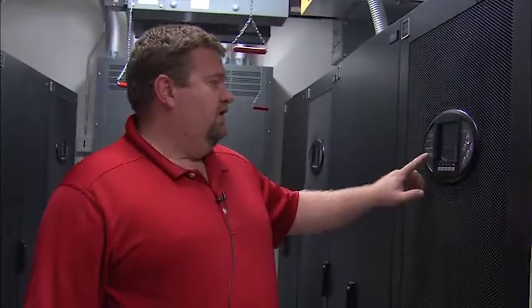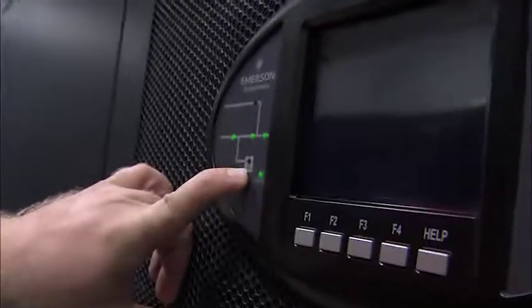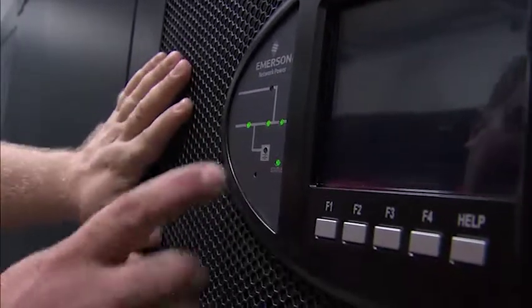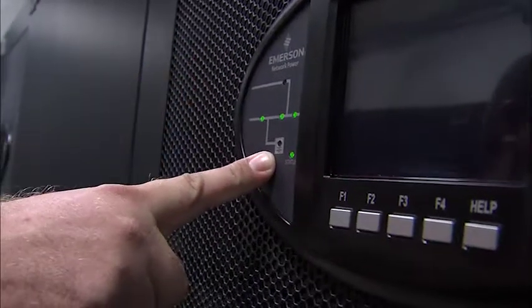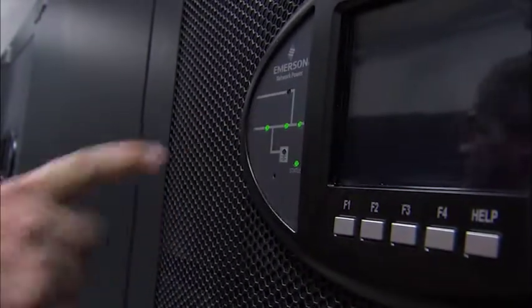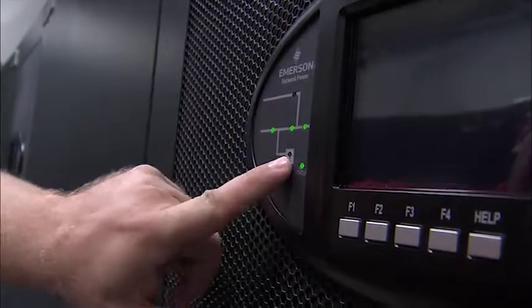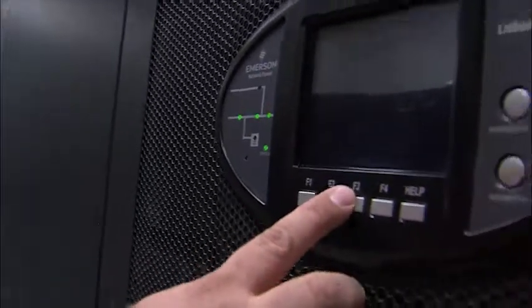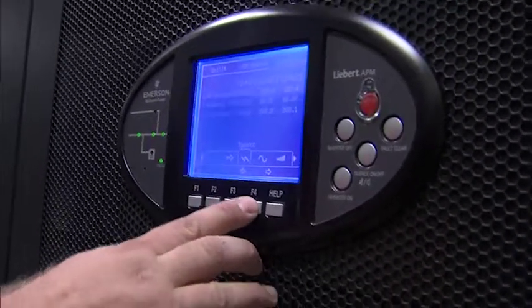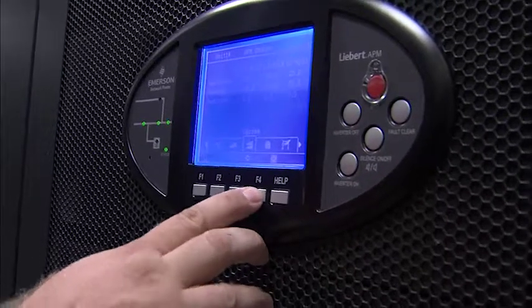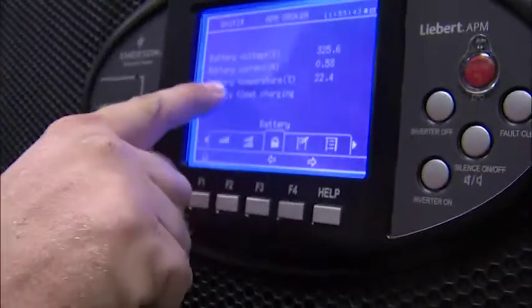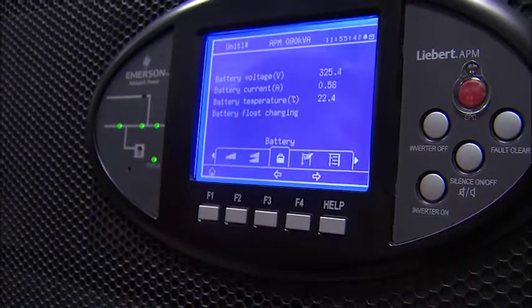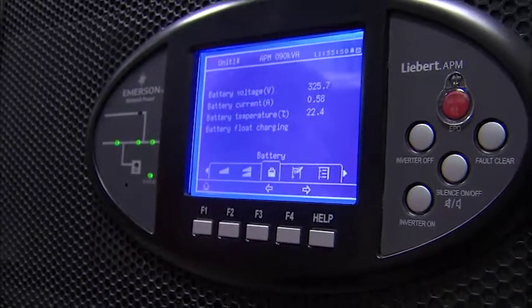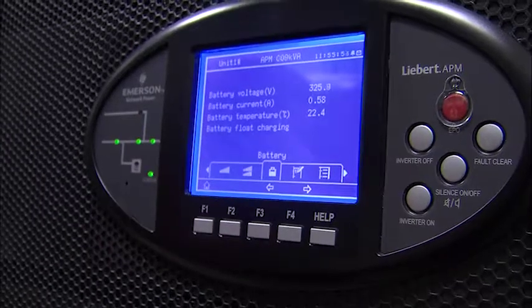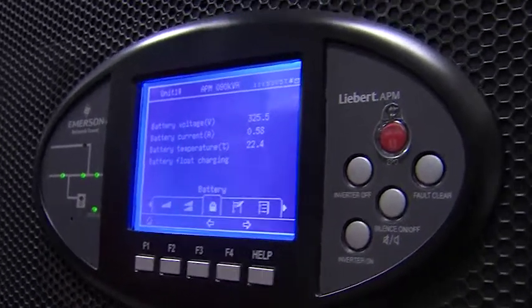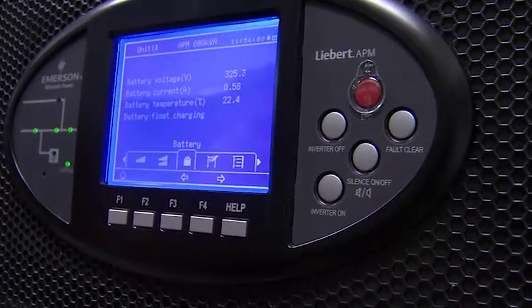So this will beep. You will see a red or an amber light on this box right here. There's a designation for the batteries. So that will come on and this will be off. So this first light will be off, this light will then be on. And it will be beeping. I'm going to show you this as well. And at that point, you can run through here. You can go to battery. And while it's on battery, it will come up and tell you how much runtime you have, which you're not going to need because your generator will come on. But it will tell you how long you have until the batteries are depleted. In this case, I think we have 15 or 16 minutes, which we won't ever use.